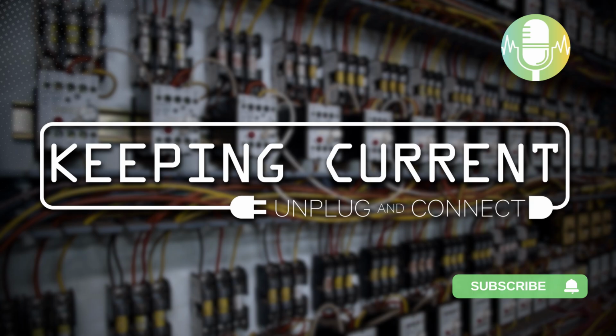Oh my God. Well, both of those are human errors—the system did exactly what it was supposed to do. Yes, the breakers didn't trip because the relay didn't trip, but it didn't trip because it was wired wrong, which is human error, not a failure of the equipment. I'd say an awful lot of what we see go wrong tends to be human error, whether it's a maintenance error or an installation error. Think about medium voltage cables—what often fails is the termination, and it's a failure because somebody didn't install it correctly, not that the termination itself went bad. Now, there are environmental factors that can play into it too, but unfortunately human error plays a lot more into these failures than we recognize.